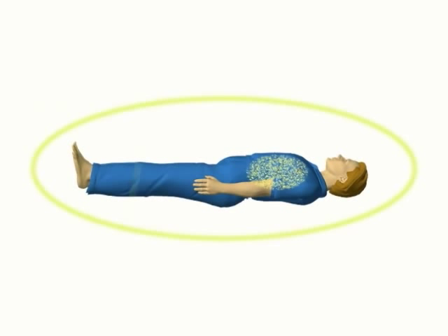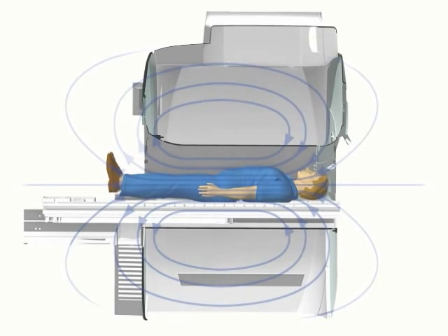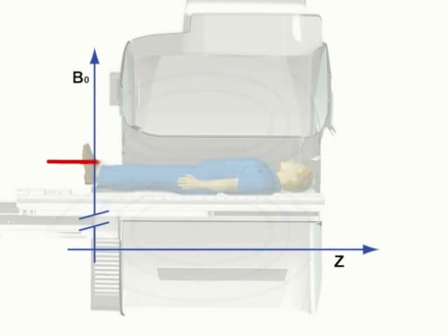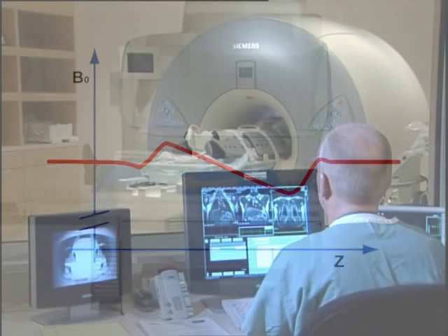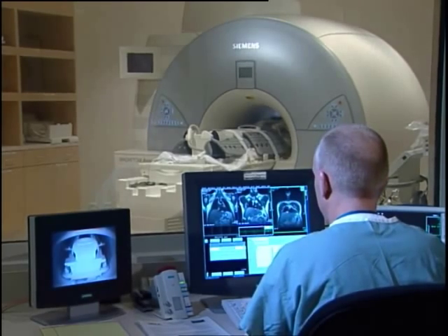Receiver coils arranged around the patient serve as antennae and detect these weak RF signals. During excitation, and while the protons are returning to the steady state, specially varying magnetic fields known as gradient fields are switched on, so that the resonance frequency of the proton varies from one region of the patient to the next. This is how the spatial distribution of the protons in the patient is coded into MR signals. A computer program analyzes the MR signals and generates an image of the distribution of the hydrogen protons in the human body. The MR unit is housed in an RF enclosure, ensuring that the very weak signals from the RF pulses are not contaminated with interference and cannot cause radio interference outside the enclosure.